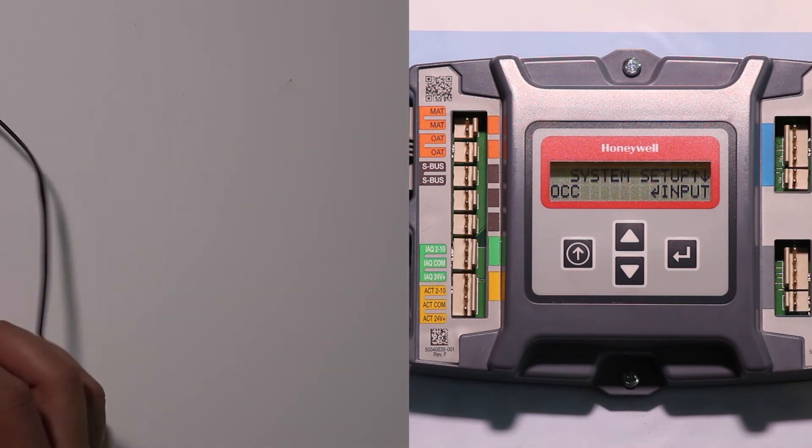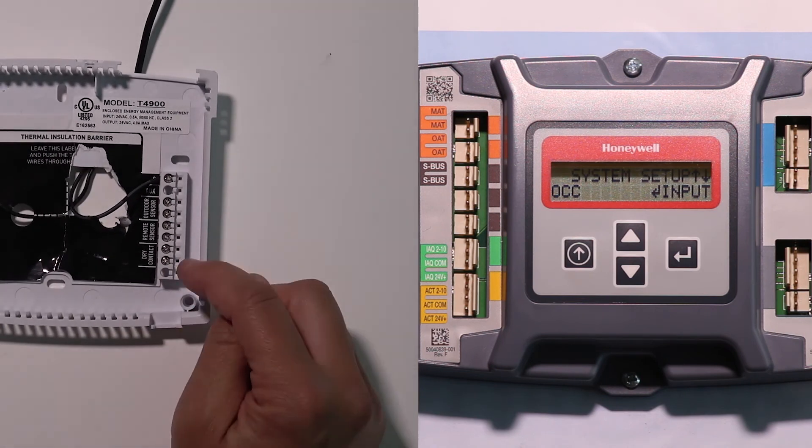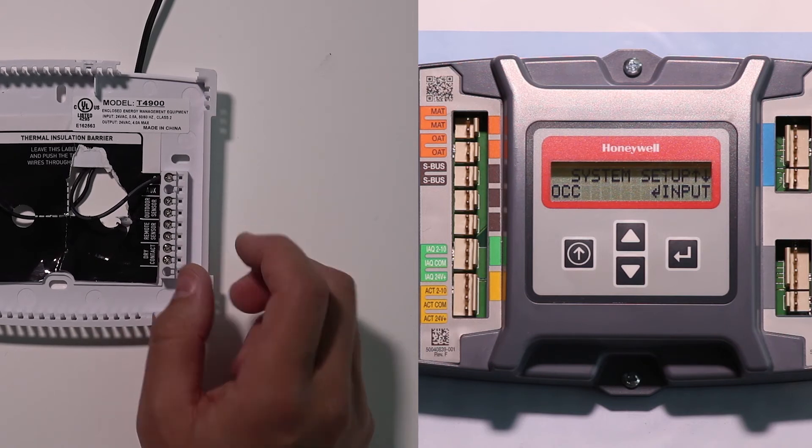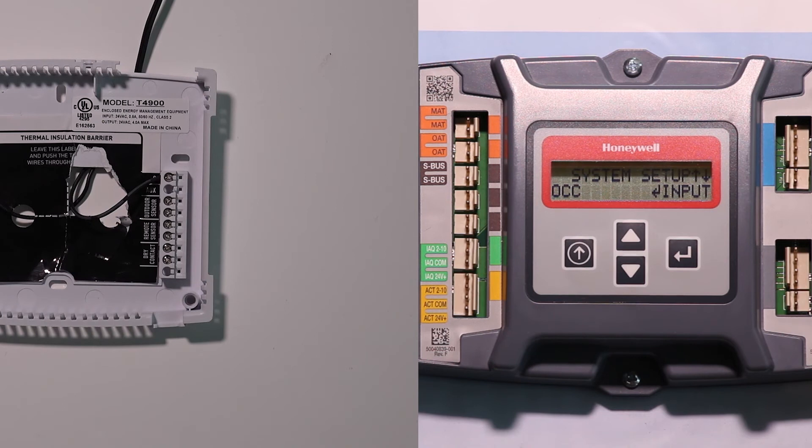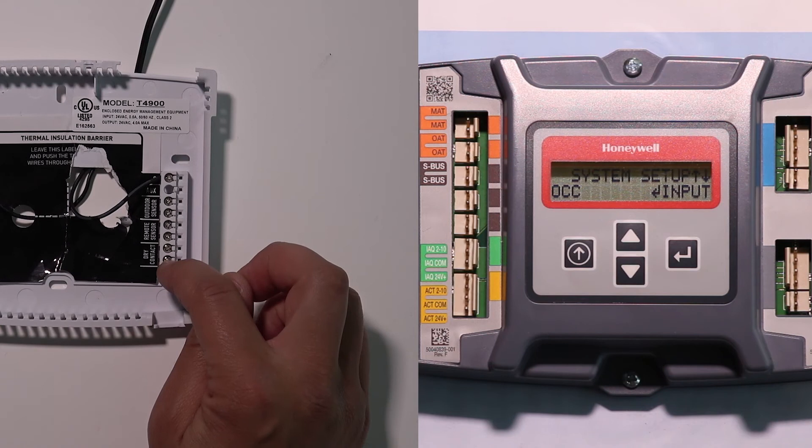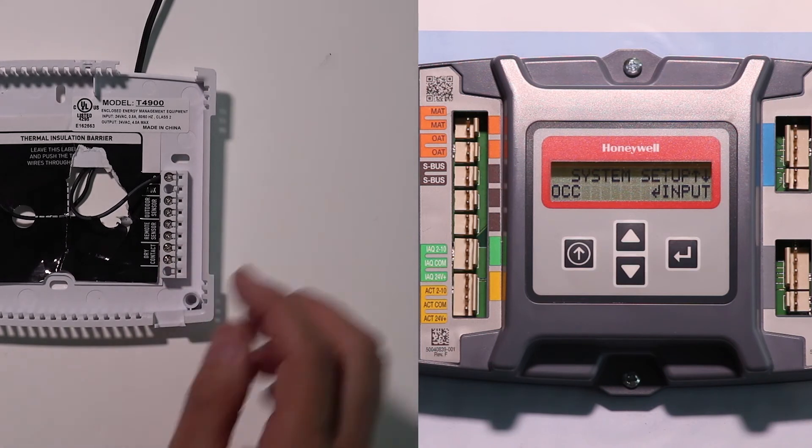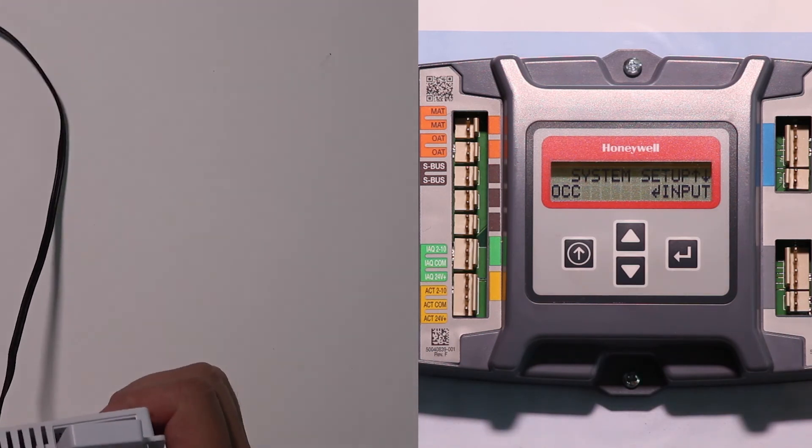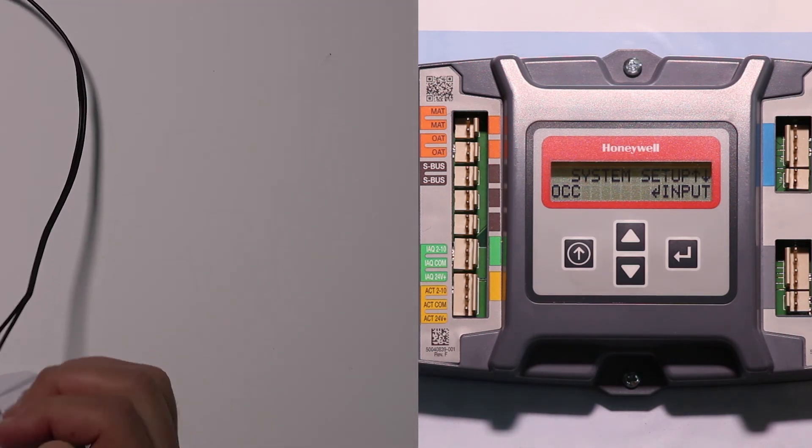So on our thermostat controller, we have this one labeled dry contact. There's two terminals there. Do not wire directly from the economizer controller to the thermostat. There needs to be an isolation relay between those two devices. So from AUX 1 output on the economizer and common to the relay, then from the relay to the dry contact inputs on the stat. That's our wiring scenario. Down in the notes of the video in the description, you'll find a link to a detailed wiring diagram and cheat sheet for this exact topic that we're talking about.